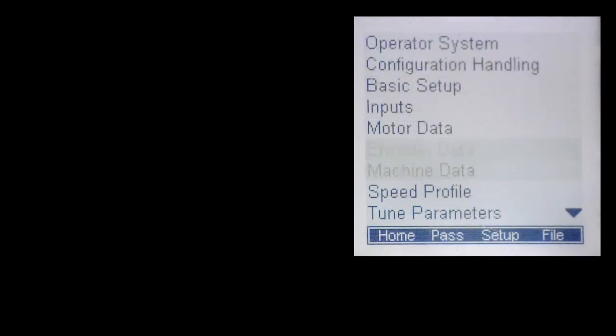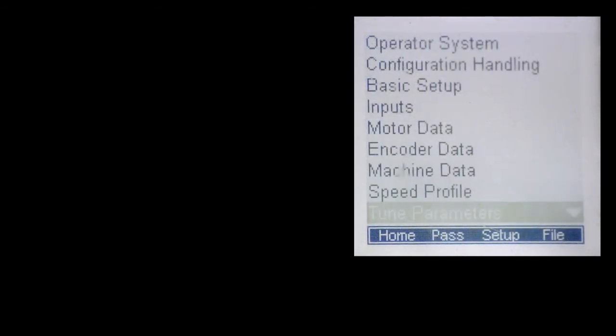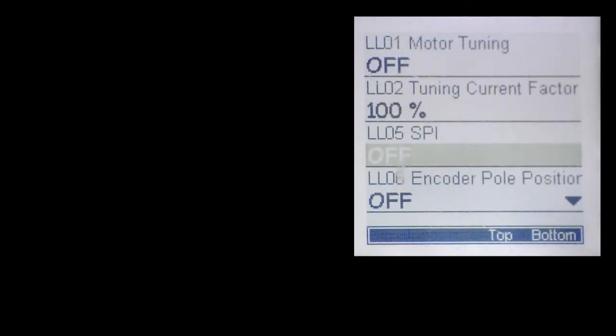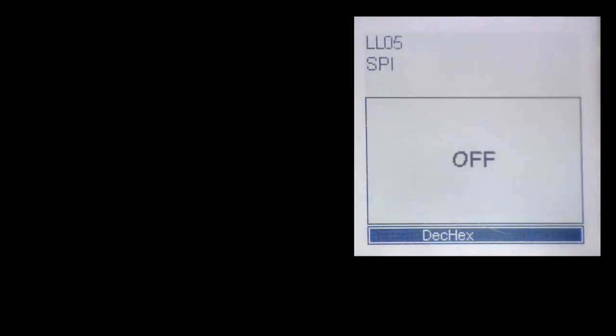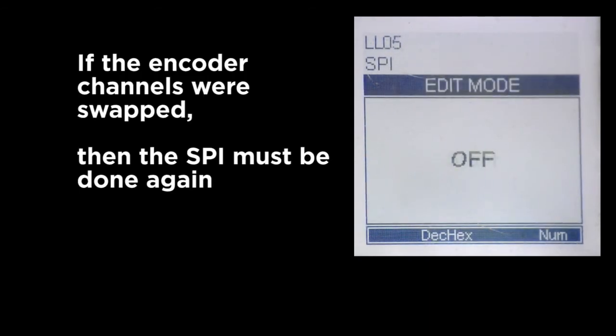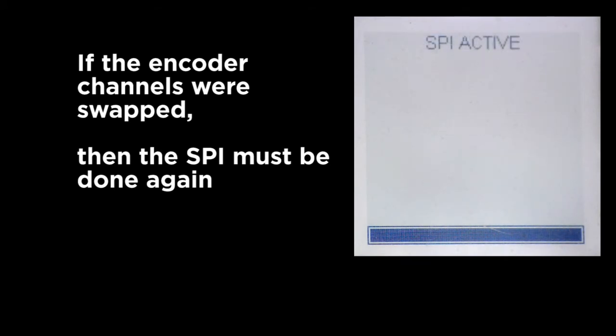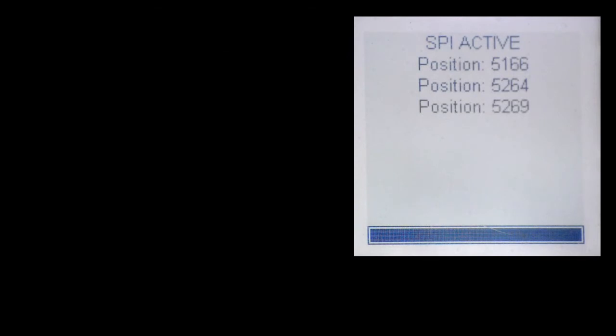From there, go back to the tune parameters and perform the SPI again. It's important that if you swap the A and B phasing of the encoder, or unswap them, the SPI process is done again, as there will be a different corresponding encoder position.